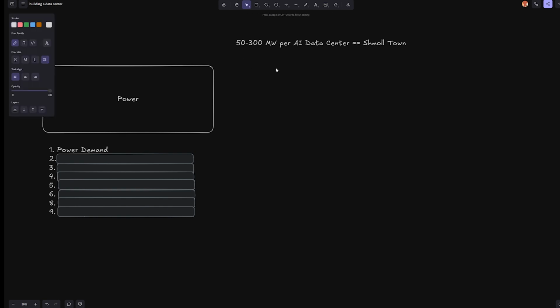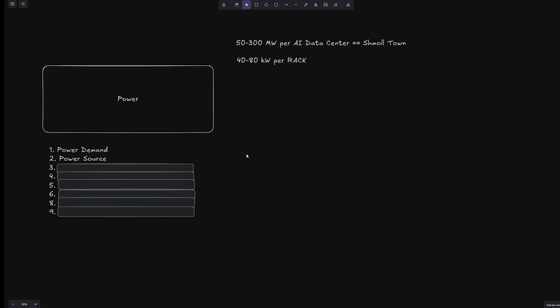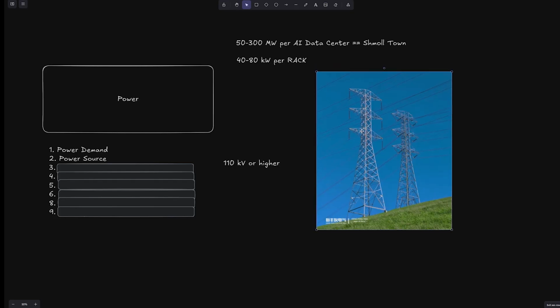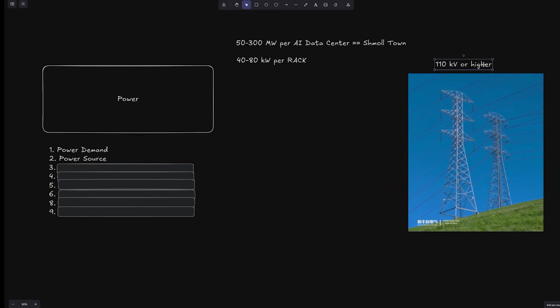A single rack of GPUs can use 40 to 80 kilowatts, which can be multiplied by thousands of racks. Power is the number one limiting factor in where and how fast these can be built. This is why the power source matters. AI data centers are connected directly to high voltage transmission lines, 110 kilovolts or higher. This is an example of a 110 kilovolt or higher power line, just if you didn't know what it means.